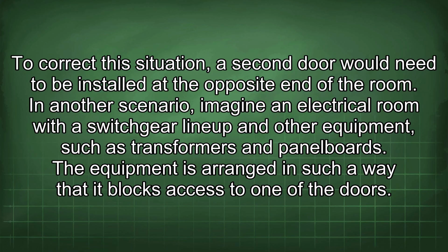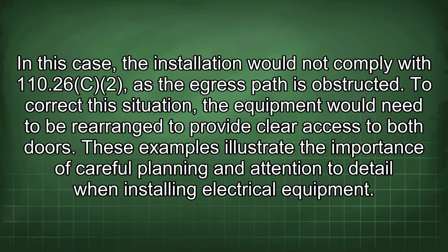In another scenario, imagine an electrical room with a switchgear lineup and other equipment, such as transformers and panel boards. The equipment is arranged in such a way that it blocks access to one of the doors. In this case, the installation would not comply with 110.26(C)(2), as the egress path is obstructed. To correct this situation, the equipment would need to be rearranged to provide clear access to both doors.